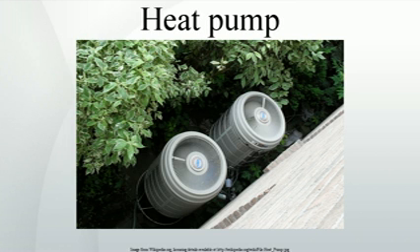Alternatively, thermal energy is transferred to water, which is then used to heat the building via radiators or underfloor heating. The heated water may also be used for domestic hot water consumption. The refrigerant is then allowed to expand, cool, and absorb heat to reheat to the outdoor temperature in the outside evaporator, and the cycle repeats.